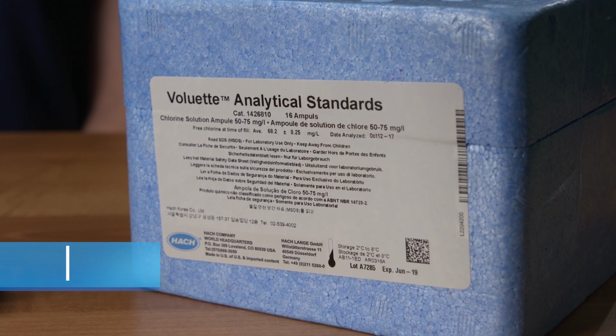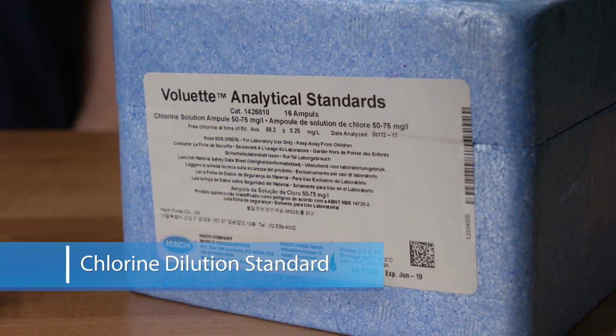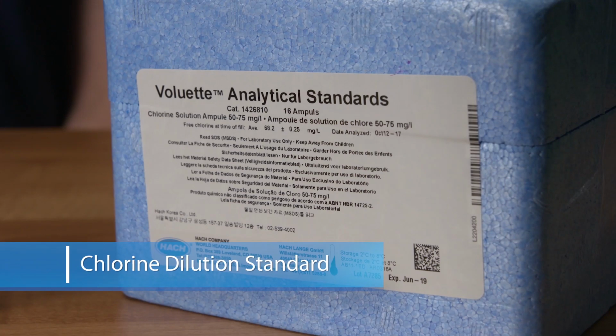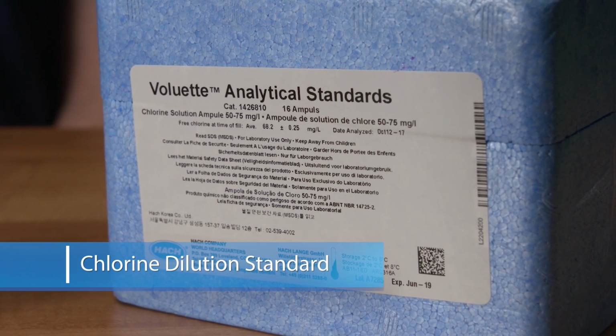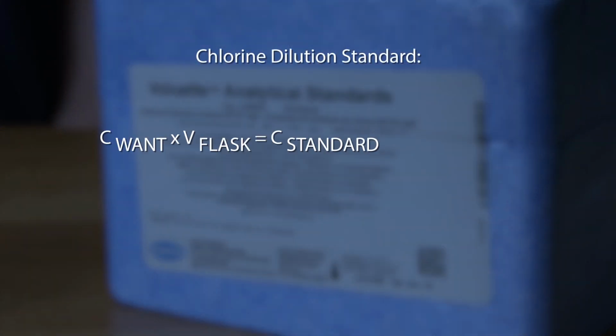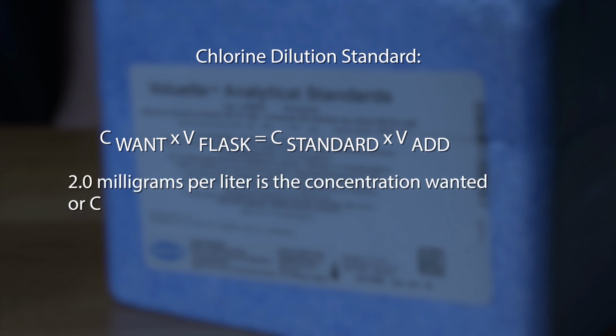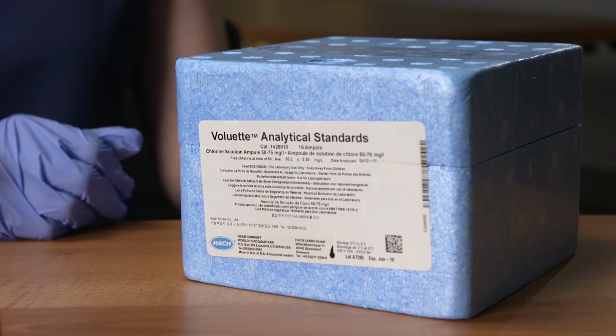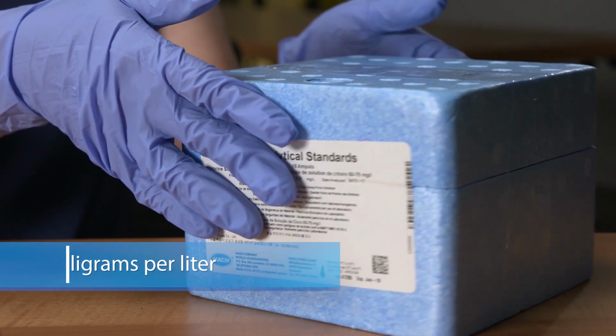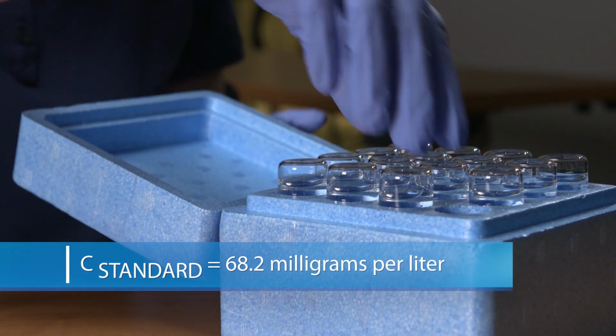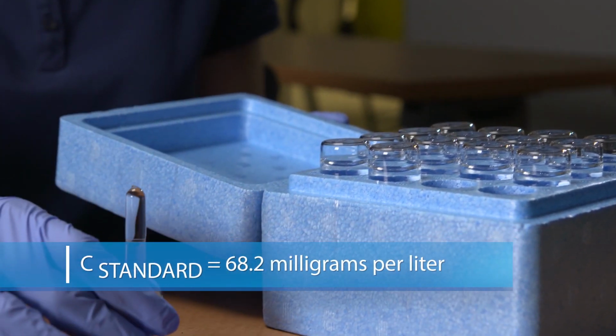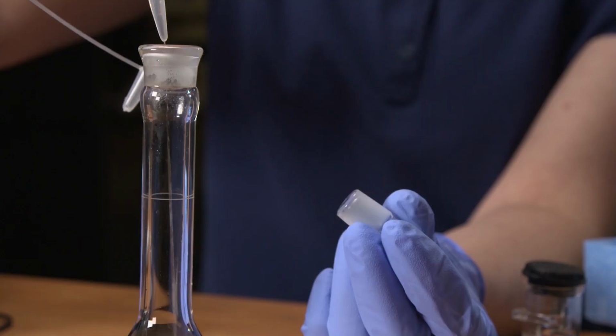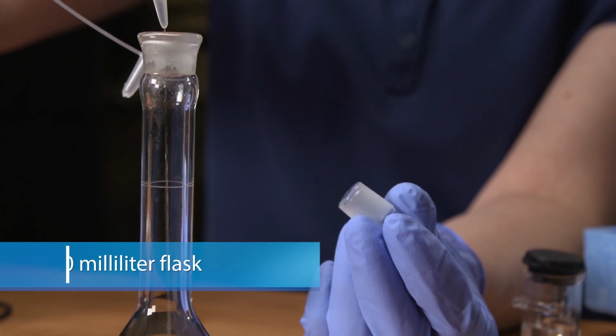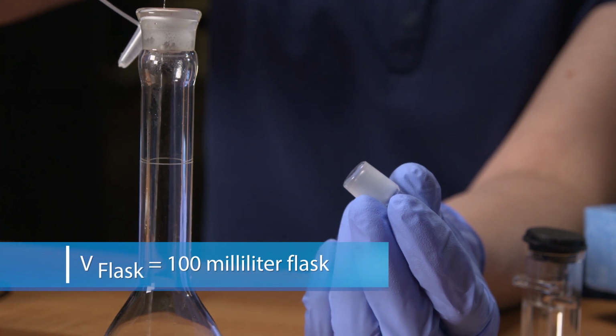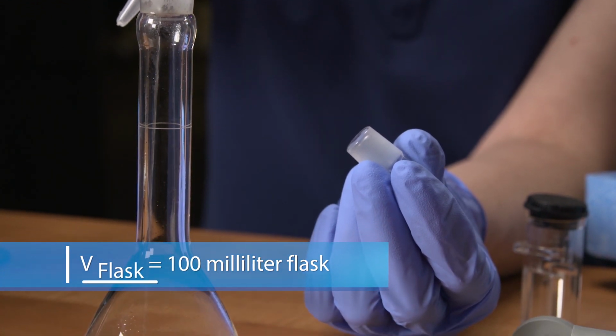Since primary standards don't come in the exact concentrations that we need, we will need to make dilutions for the concentrations that we need. In this example, we will be making a standard of 2.0 milligrams per liter, which is the concentration wanted, C want, in the equation. We check the label to find that our standard ampule contains a 68.2 milligrams per liter solution, which is C standard in the equation. In this example, we will be using a 100 milliliter flask, which is the volume of the flask, V flask, in the equation.